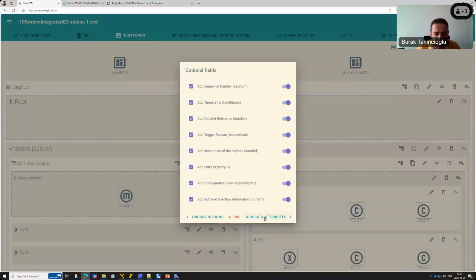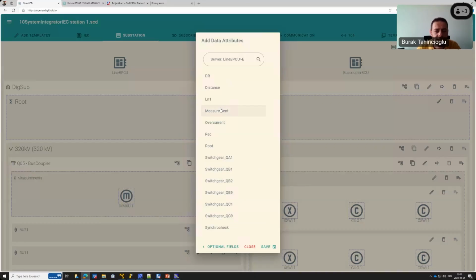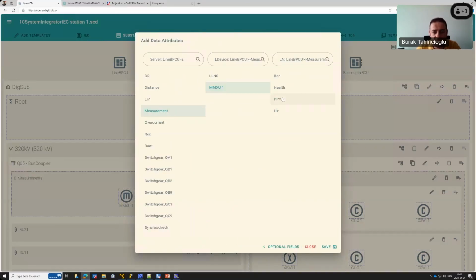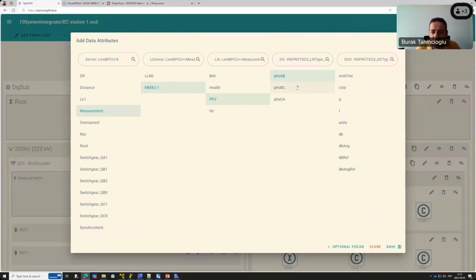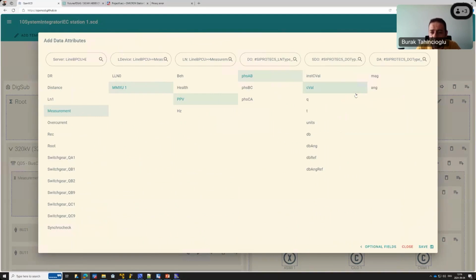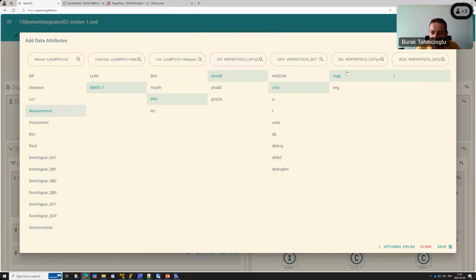I'll skip this option, it's not so important. I want a data set consisting of data attributes like the phase-to-phase voltages. I want always the C value, not the instantaneous value, only the magnitude of it—a structured data object with more data attributes, including the basic data attribute type, but with the measurement value together with the Q. I've done this for BC, CA, and also for Hertz, the frequency, and saved it.